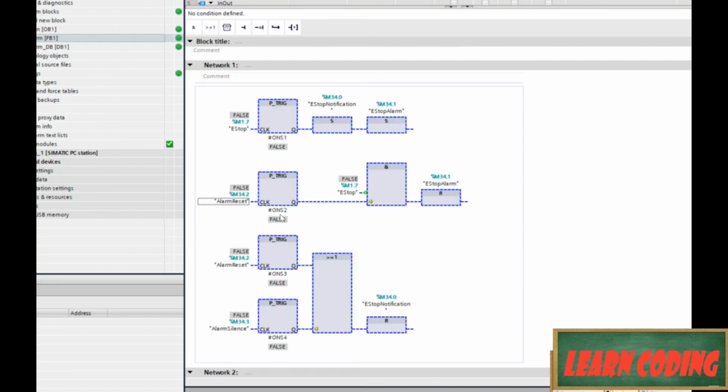So this is what it looks like when you chain function blocks together. You see, it's kind of like ladder logic. You've got a line running through them. It almost works like a little rung. But we're actually doing things conditionally, one right after another. And we can do simultaneous things at once, like setting 2 bits, whereas in ladder logic you generally don't do that. In some environments you're allowed to, and some you're not, but it's never a good idea. In function blocks, however, these things are made for that, so it works great.